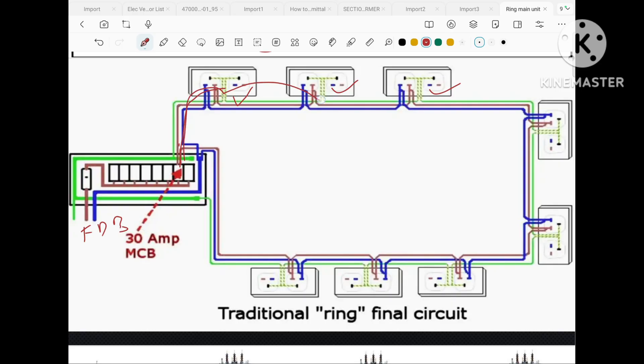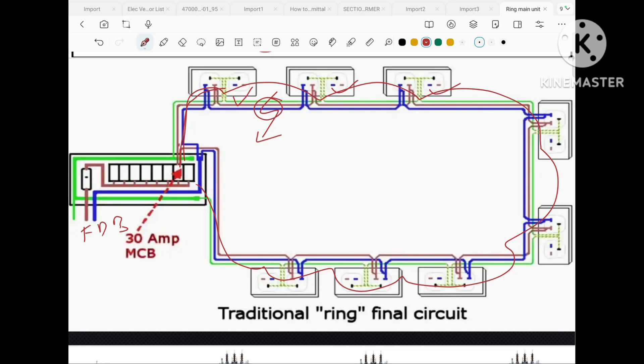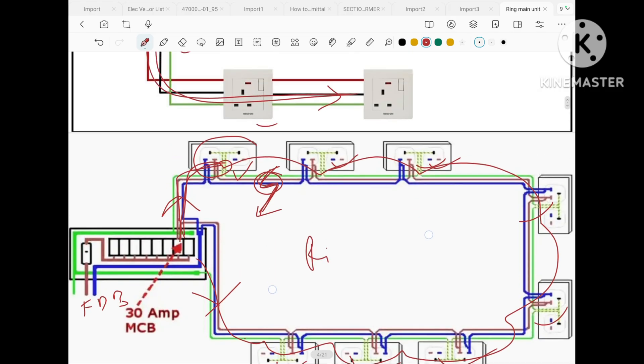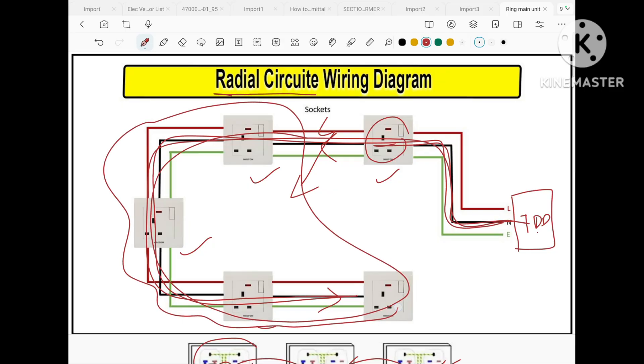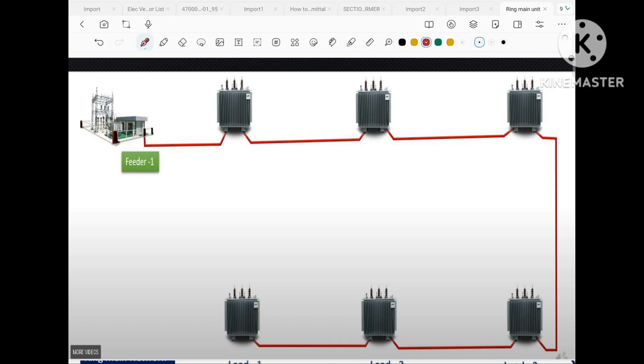But suppose these 13 ampere sockets are connected with the final distribution board in such a manner that it initiates from the distribution board to each socket and it ends also back to the distribution network. If any power supply fails due to a fault in the wire, the power supply will still reach all of the sockets — from this way and from the other direction. Even though there is a fault in the wire the power supply still reaches all sockets. This is the importance of ring. But in case of radial, if there is a fault, the power supply will reach up to that point and after that all other sockets will be disconnected from the power supply.